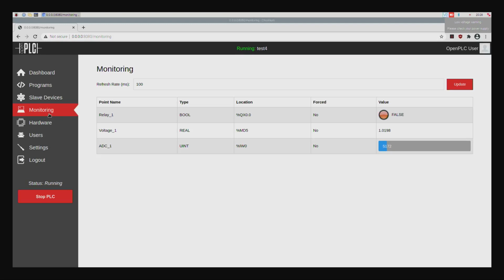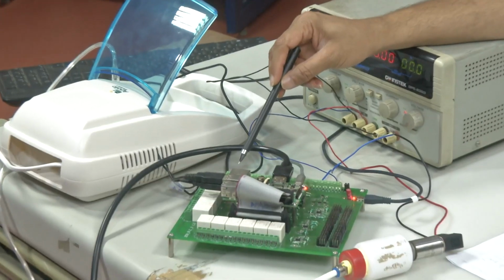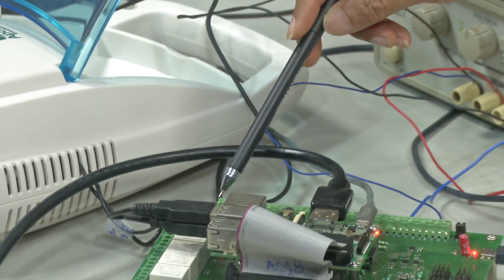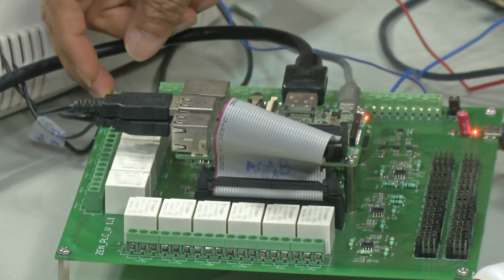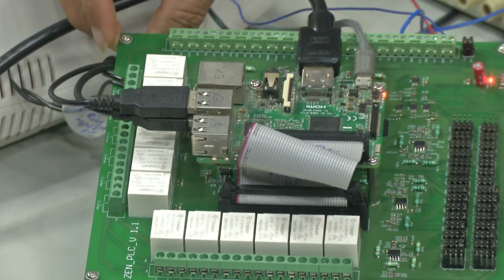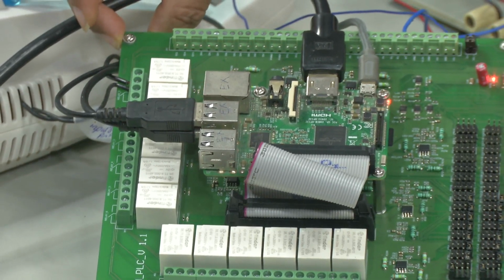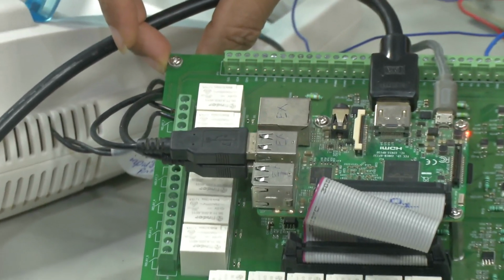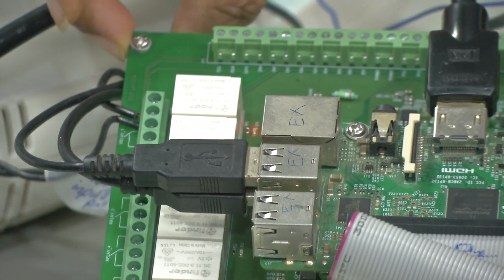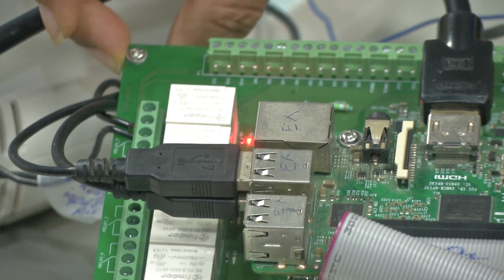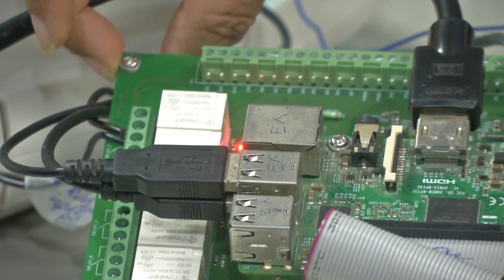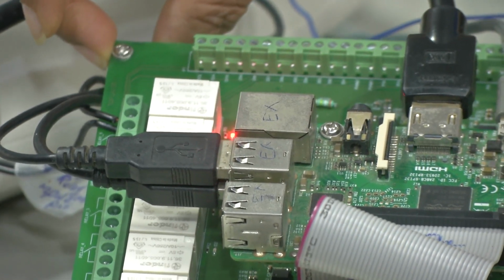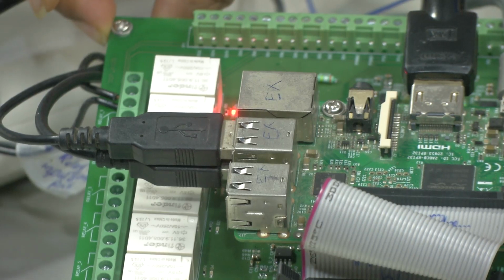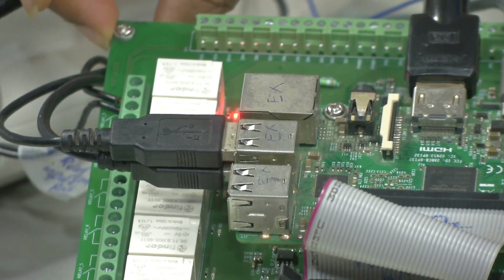Clearly on-off is happening, and one more screen of interest would be to look at this relay. This is the relay getting actuated — you will actually see it turning on. There you are, that is the relay which is controlling the nebulizer. The nebulizer's power is being gated through this relay, switching on and off.